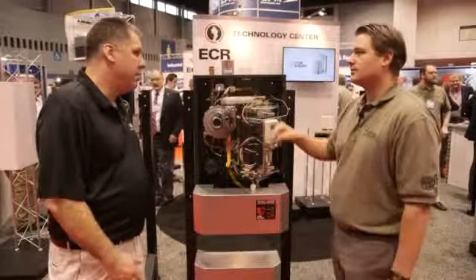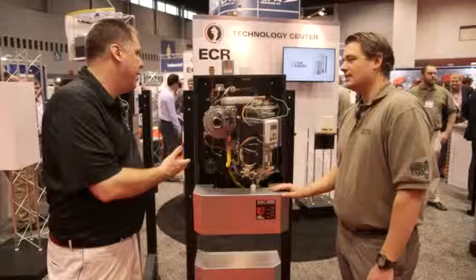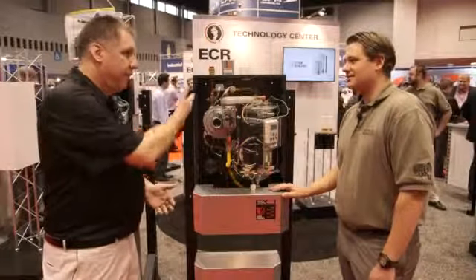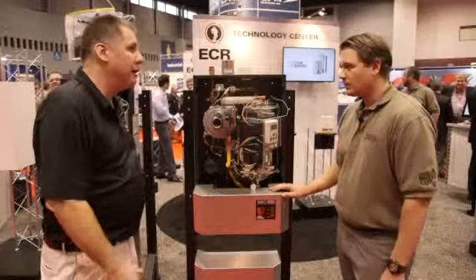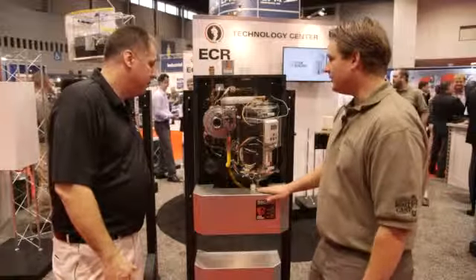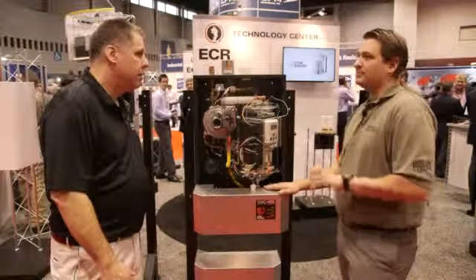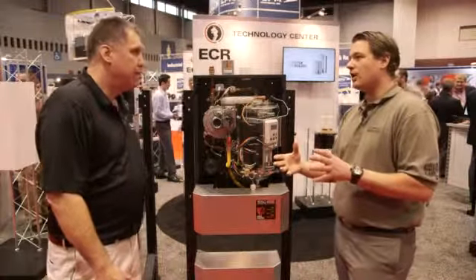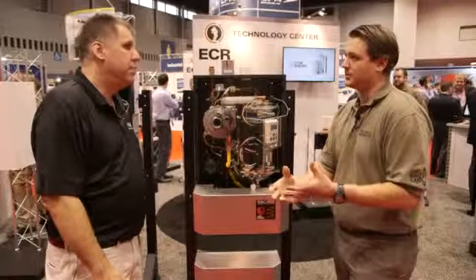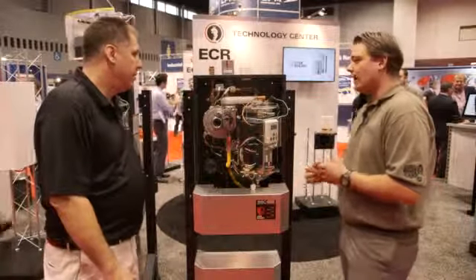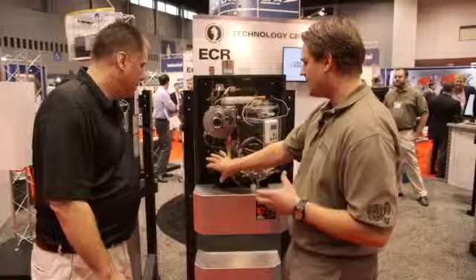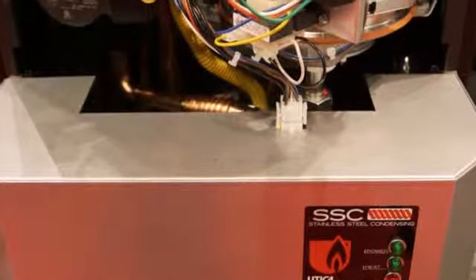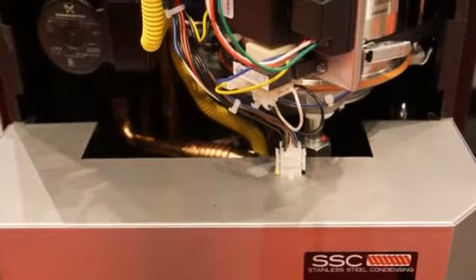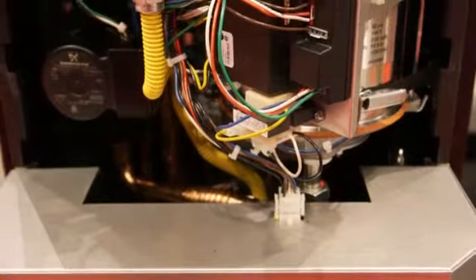Well, that's code in my jurisdiction. We have to provide them. Now that it's factory provided, that makes it a lot easier for us as a contractor. It's a great feature for these boilers, and a lot of places now, even if they didn't have a low water cutoff in the code, they're starting to introduce that, so it's becoming more and more prevalent. The contractors really like the primary, secondary built in, because there's some confusion sometimes as to where do I make that, how close do I put the tees, so we've done the engineering for them inside the boiler.